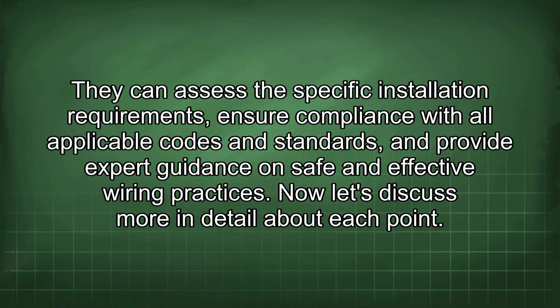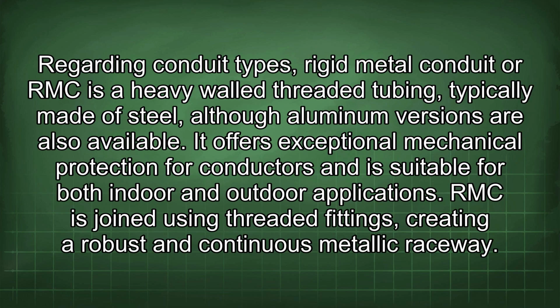Now let's discuss more in detail about each point. Regarding conduit types, rigid metal conduit or RMC is a heavy-walled threaded tubing, typically made of steel, although aluminum versions are also available. It offers exceptional mechanical protection for conductors and is suitable for both indoor and outdoor applications.